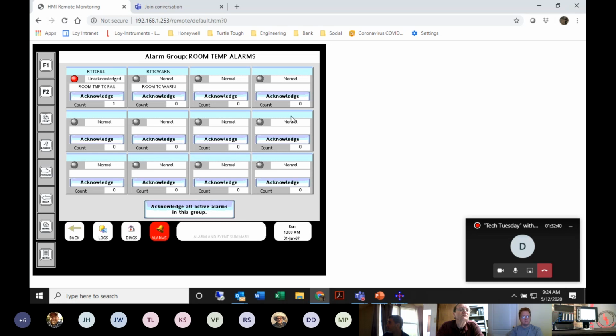and now I can get a full grouping of all of the room temperature alarms that is under that group. And I can either acknowledge it as a group or I can acknowledge it as an individual. And now it's acknowledged, but it's still an alarm, so we still have the red bell ringing at the bottom. Those are a couple of the standard displays that are really, really good for troubleshooting.